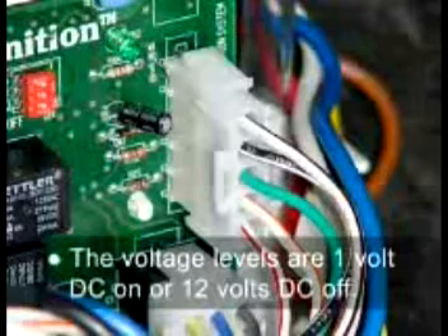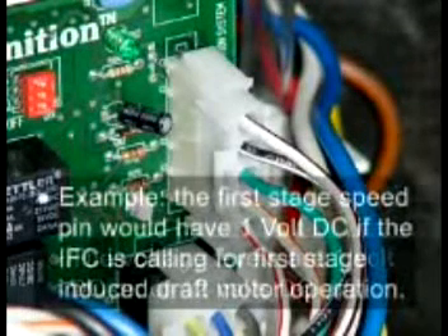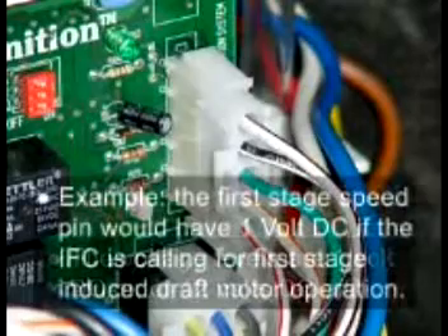The IFC tells the vent motor whether to operate at first stage speed or second stage speed. The stage signal is sent out on the 5-pin IFC plug. The voltage levels are 1 volt DC on or 12 volts DC off. For example, the first stage speed pin would have 1 volt DC if the IFC is calling for first stage induced draft motor operation.